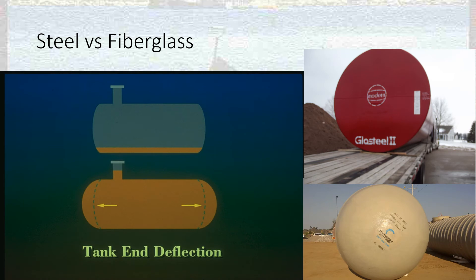When looking at a steel tank versus a fiberglass tank — the two major materials most gas station tanks are built from — you can identify them by their ends. If a tank has flat ends, it's a steel tank; you can see the flat end on this tank here. If it has a rounded or convex end, that tells you it's a fiberglass tank. This is a quick and easy way to identify tank material whether you're looking at drawings or in real life.